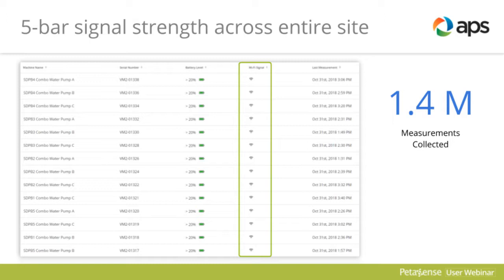And so far we've got roughly about 1.4 million data points collected. Now that data point represents the fact that these sensors are 4-channel sensors. They're full-blown triaxial sensors, so they got 3 channels for that, and there's a 4th channel for surface temperature. So those 4 data points coming through about every 3 hours is how we've got things typically set up. Pulling data now for about 6 months, we've got a good 1.4 million or so data points. That compares to if you were taking those on a route-based setup, you'd be about 6,000 route-based measurements.